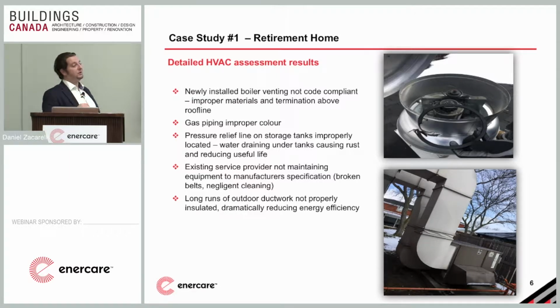The other thing we noticed was there's not just code requirements for this scenario, there were also manufacturer requirements. The boiler manufacturer required a special coupling be put in for the first 12 inches of the venting, and that coupling was not there. That's not something an inspector would care so much about or really even catch.